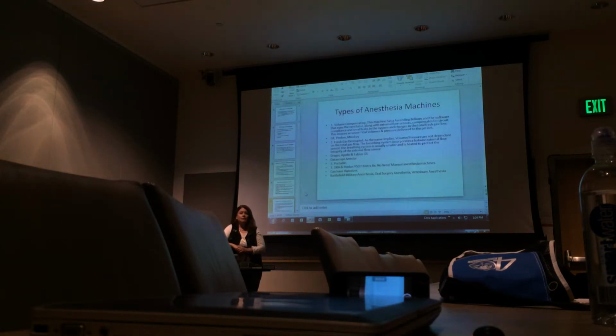Three types of anesthesia machines: volume compensating, fresh gas decouple, and the portable machine. Volume compensating will always have an ascending bellows. That's your GE machine, Penlon, Mindray. It has software and external flow sensors that compensate for changes in the delivered volume to the patient. They've become highly accurate nowadays, so it doesn't matter what flow you dial in. It used to be with the volume compensating units that the higher the flow, the higher the tidal volume. Now it has algorithms in the ventilator that try to keep it at what you set it.